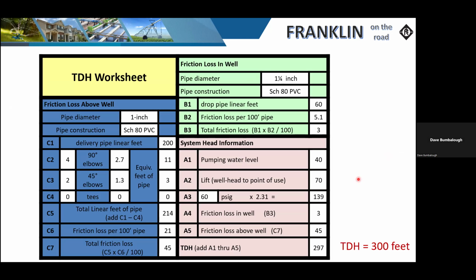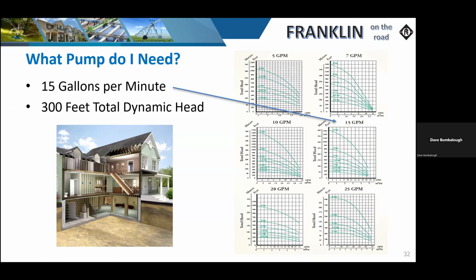And then as our system pressure, we start adding all those up and plugging those numbers in. We eventually come up with a total of 297 foot of head loss. I round that up, and in this case, for our TDH, I'm going to use 300 as our target point. So next, we're going to look at an actual curve. Okay, and I'm going to try to get as close as I can to that desired gallons per minute we require for that system. So when we look at this, the 15 will definitely hit what we need. Now I can get 15 out of this 10.